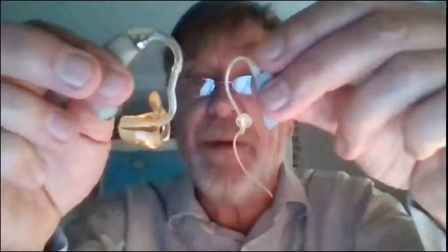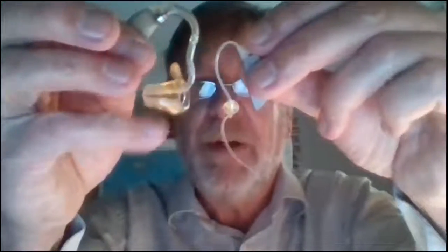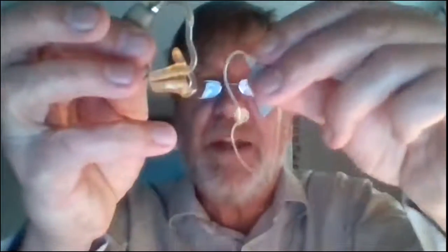That's the diameter. Okay? When you have this kind of hearing aid, this is called thin tube, because if I hold this one up, look at how thin it is in comparison. And this one is less than 1 millimeter diameter, about 0.8 to 0.9 millimeters. This one's 2 millimeters diameter. Okay, you can see the vents clearly, bottom here, and in the dome, you can see the holes right there. All right, very good. We're getting someplace here.